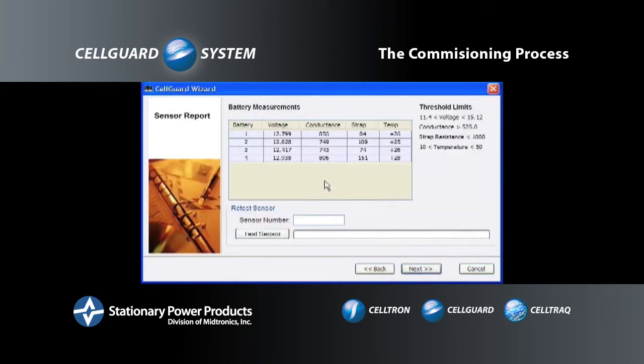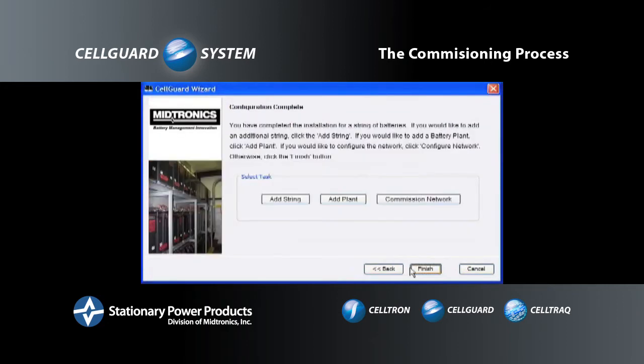The wizard allows you to review the readings from each sensor for the corresponding battery's voltage, conductance, strap resistance in microohms, and temperature in degrees Celsius. If any of the readings are suspect, you can retest the battery by entering in the sensor number and then clicking the Test Sensor button. If all the readings look fine and there is no reason to retest, then click the Next button.